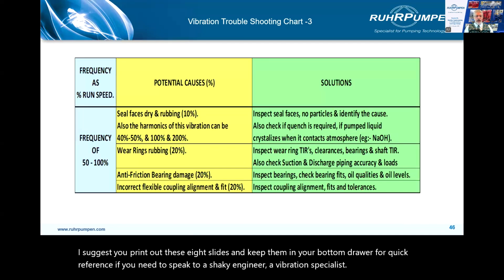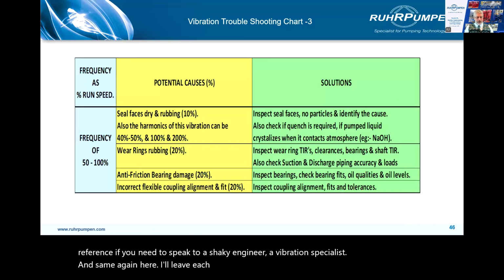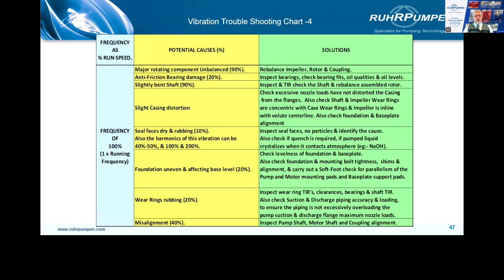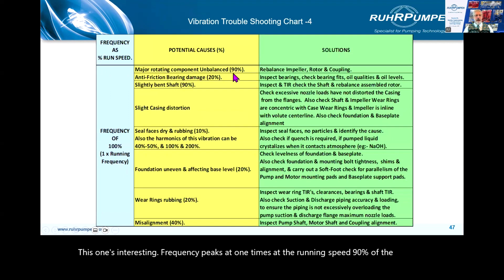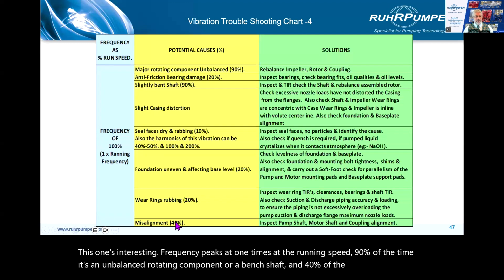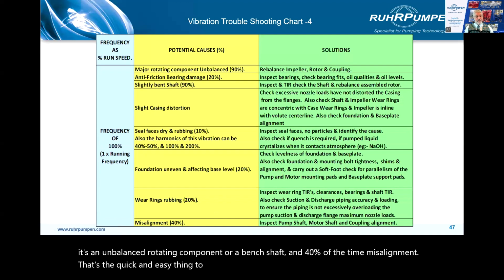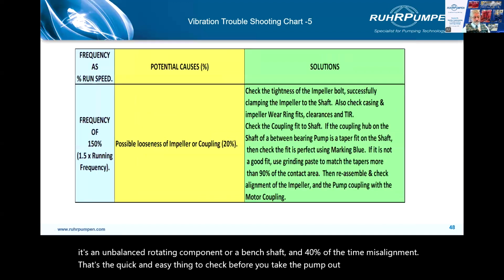And same again here. I'll leave each one up about 20 seconds for you to have a brief read. This one's interesting. Frequency peaks at 1 times the running speed. 90% of the time, it's an unbalanced rotating component or a bent shaft, and 40% of the time, misalignment. That's the quick and easy thing to check before you take the pump out of service.